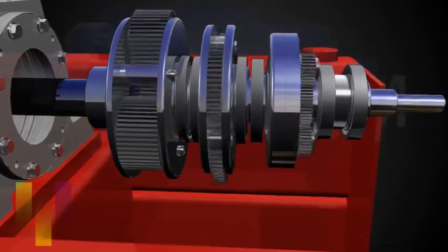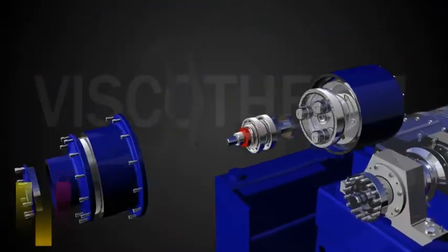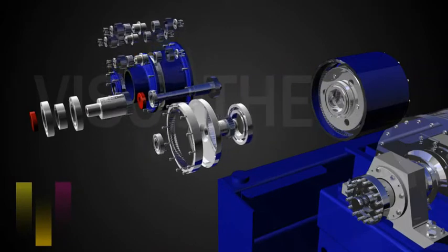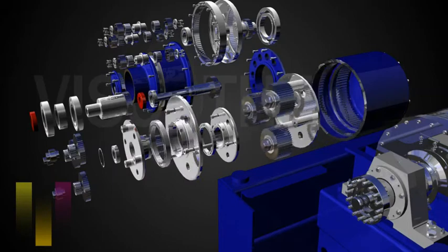Overheating of gearboxes is a common problem because of inadequate lubrication of the gears located in the center of the box. The centrifugal force distributes the oil towards the outside wall of the gearbox, away from the center gears.